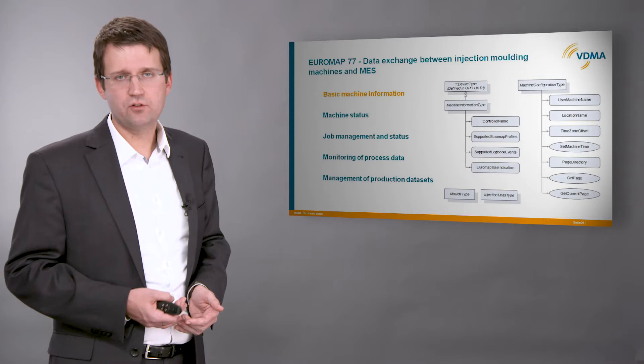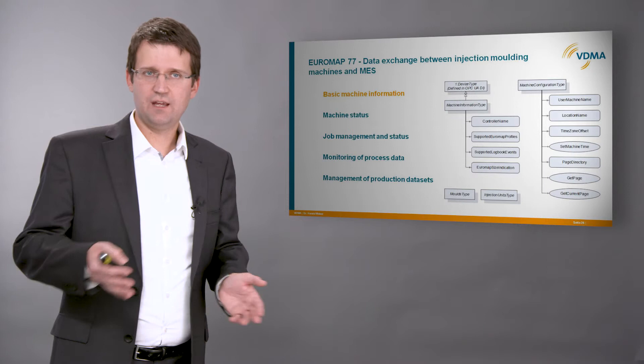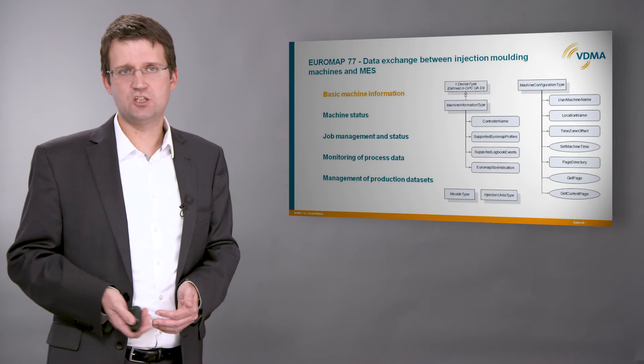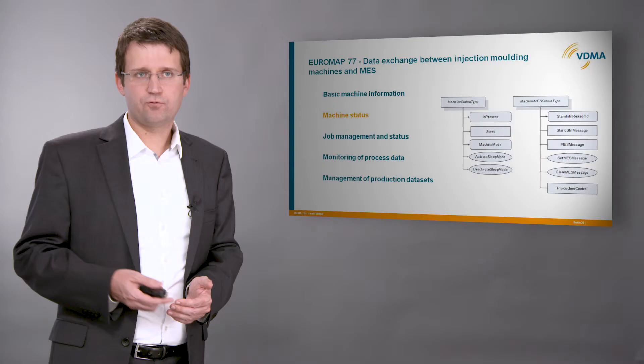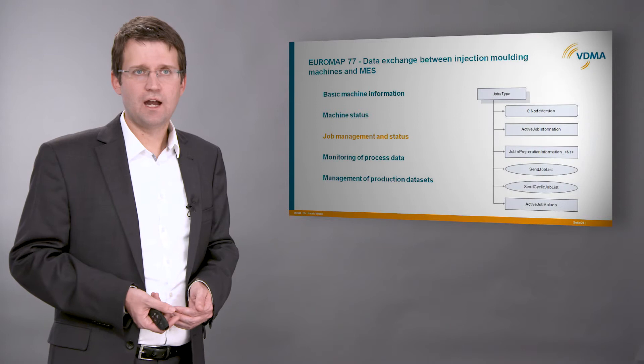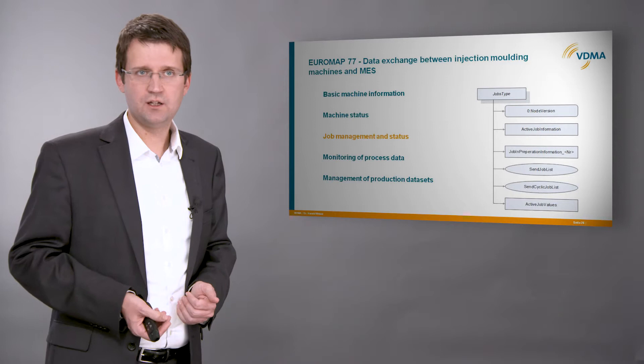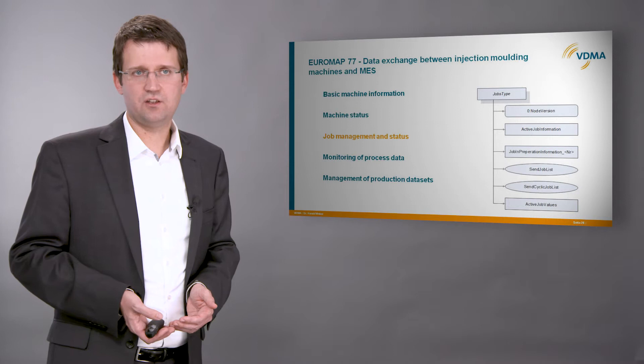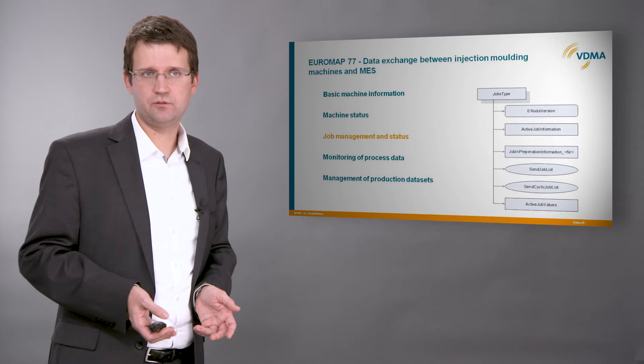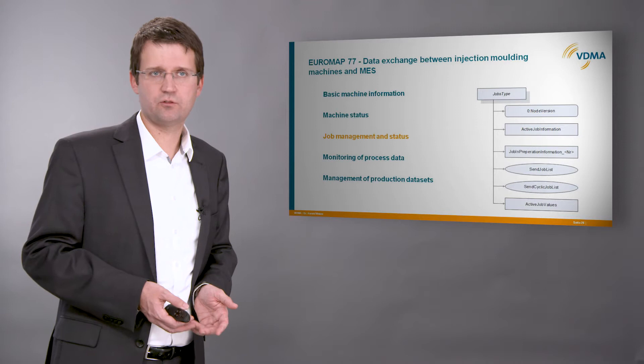What is the functionality included in Euromap 77? First, we have some basic information about the injection molding machines — for example, the name of the manufacturer, the model, but also the current configuration, like which molds and injection units are installed. The next information block is the current status of the machine: is the machine in manual mode or automatic mode, which operators are currently logged in, what is the reason for a current standstill. After this more or less static information, there is a block for the complete management of jobs. A job may be, for example, to produce 10,000 mobile phone cases. Euromap 77 includes basic information on the current and possible following jobs — name, description of the part, used molds and material — as well as a job status: if the machine is in startup phase or already producing parts, how many good and how many bad parts have been produced.